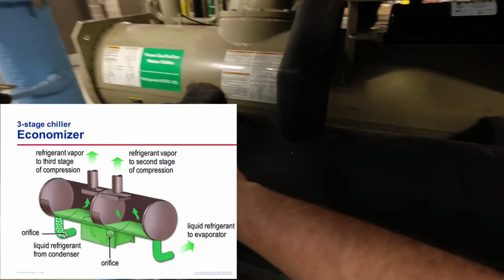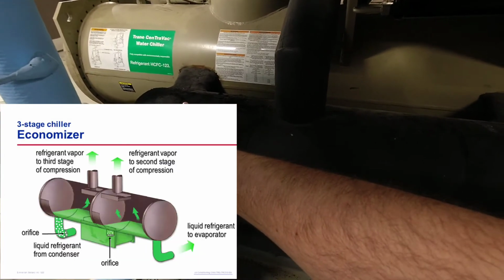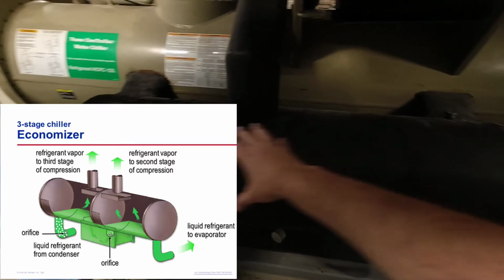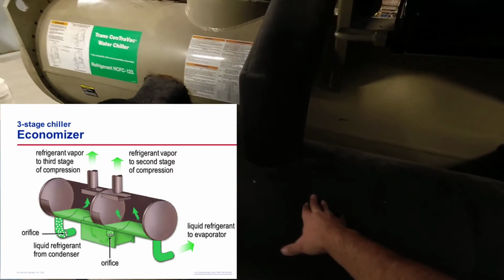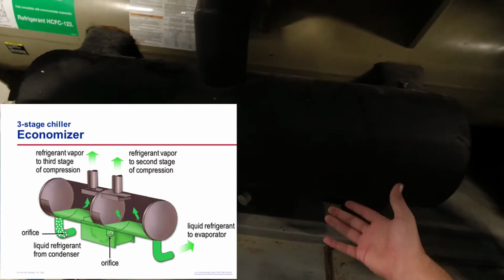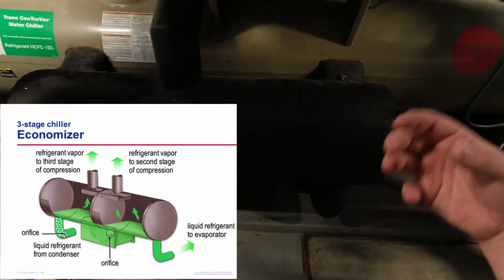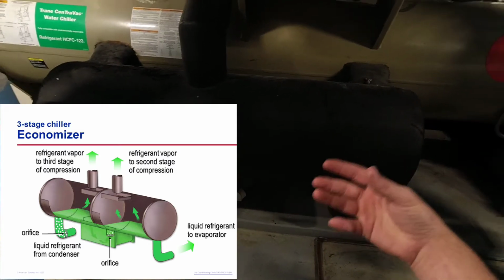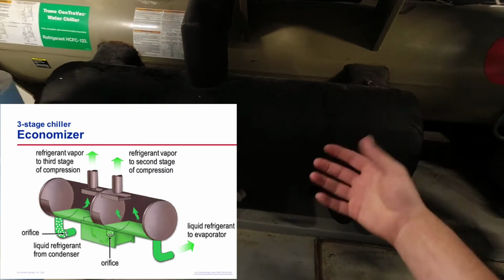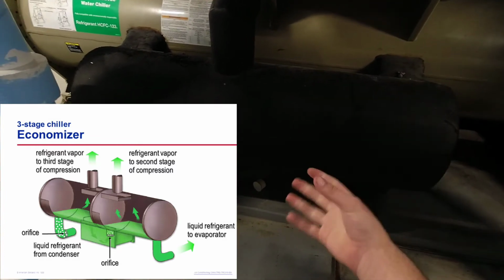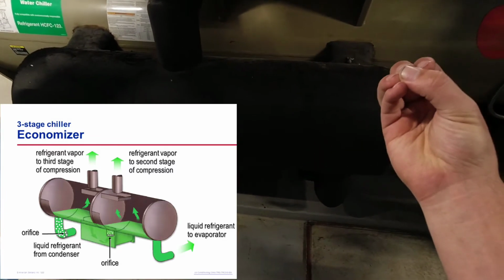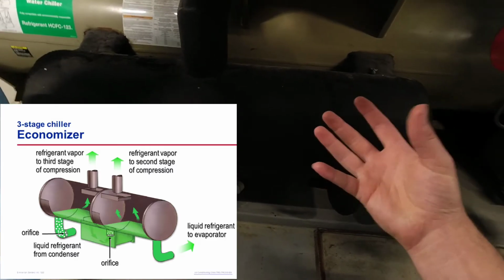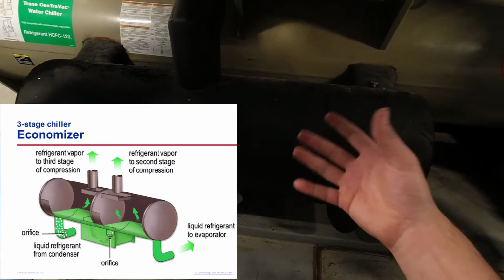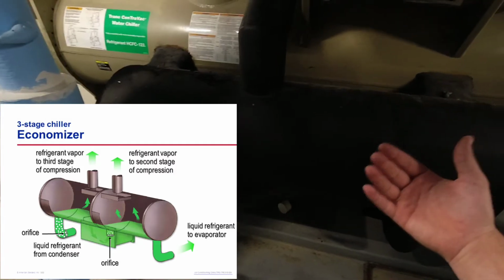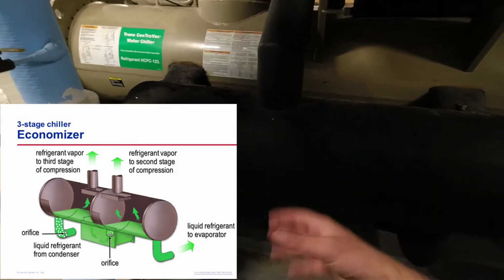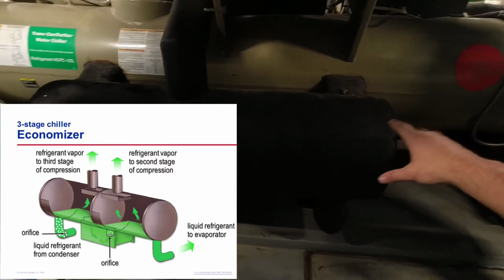So what's happening here is this economizer is allowing flash gas to collect in the top. Leaving a TXV, we have to flash some of the refrigerant in order to start creating cooling, because we have such a great pressure drop and a larger opening that we have to fill the void inside the space of the pipe. That's basic theory on a TXV. Well, we kind of have the same principle here.